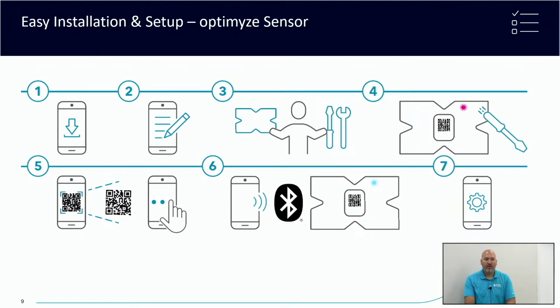And then step 7 is just telling you to basically, what are you installing the sensor on? How often do you want to take readings? There are pre-built-in standards within the sensor, so you don't have to understand vibration or temperature levels. We have ANSI HI standards or ISO standards in there that are going to predefine certain thresholds for pumping applications based off of the horsepower size and pump type you select within the setup portion. However, if there's a different standard that you want to use, or let's say you just have a specific value in mind, you can set custom thresholds as well. But there are pre-built-in standards, so you don't necessarily have to be familiar with thresholds on what's good and bad.